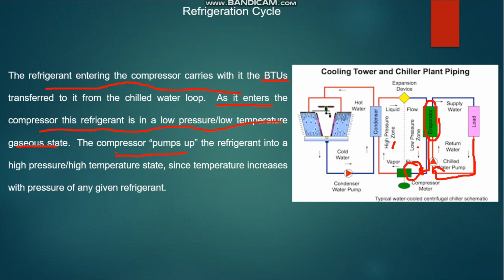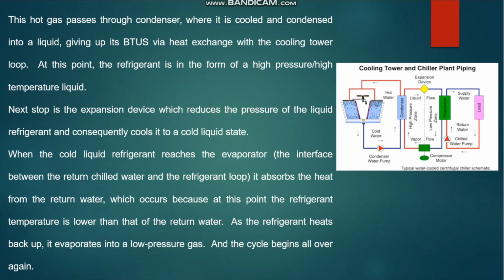The compressor pumps up the refrigerant to high pressure and high temperature, because the pressure is directly proportional to temperature. This high pressure, high temperature refrigerant gas passes through the condenser. At the condenser the heat exchange with the cooling tower is happening. At this point the refrigerant becomes a high pressure, high temperature liquid because of the condensation process happening here. The next step is the expansion device, which reduces the pressure of the liquid refrigerant and consequently cools it.